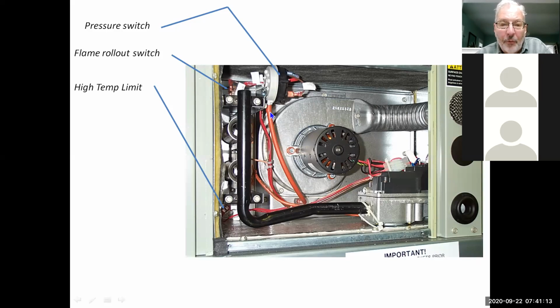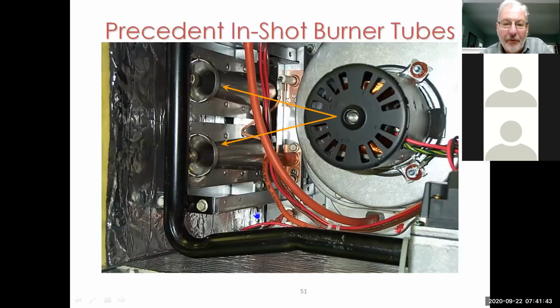On the precedent models, we have spark ignition and a flame sensor. And then we have a rollout, which is up here. And we have a temperature limit, which is down here, okay? So we run the inducer, we pull in the pressure switch, we start the spark ignition, and after, I think it's a 15-second pre-purge, the gas valve should energize, we should light the flame, and the flame sense should take over and sense flame at that point, okay? And this is kind of what it looks like if you haven't seen one.